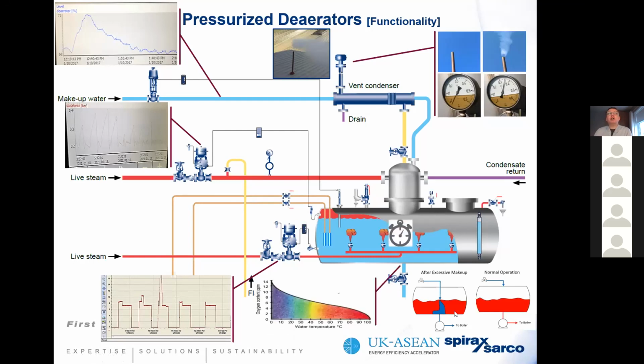Again, look at time, retention. So in other words, again, you'll find that depending on the water temperature determines how much oxygen is in the system. And what you want to do is get to a scenario here where you're adding water at a proportional rate to consumption. So you have the common temperature here, or isothermal temperature. So in other words, all the water is at the same temperature, and you're feeding basically deaerated water to the boiler. And again, this is a common failing we're finding in steam systems, which has an energy impact.